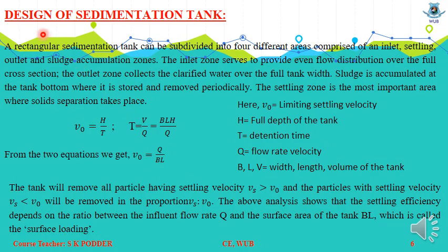Now we look at the design of the sedimentation tank. A rectangular sedimentation tank can be subdivided into four different zones: the inlet zone, the settling zone, the outlet zone, and the sludge zone. The inlet zone provides even flow distribution, the outlet zone collects clarified water, sludge is accumulated at the tank bottom and removed periodically, and the settling zone is the most important area where solid separation takes place.